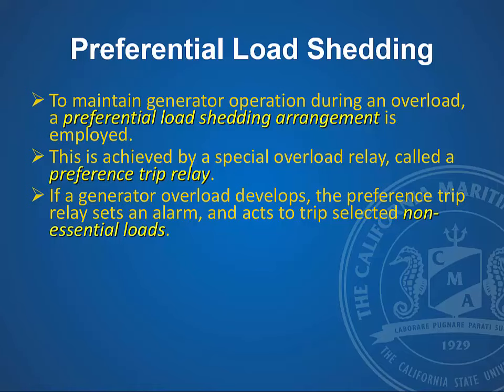Those are going to be things like your air conditioning and different loads that if they trip will not endanger the vessel. And by tripping these loads, you reduce the load on the generator to give another generator more time to come on. But that also means that you as the operator are going to have to go down and reset all this equipment. And these are called preferential trips.